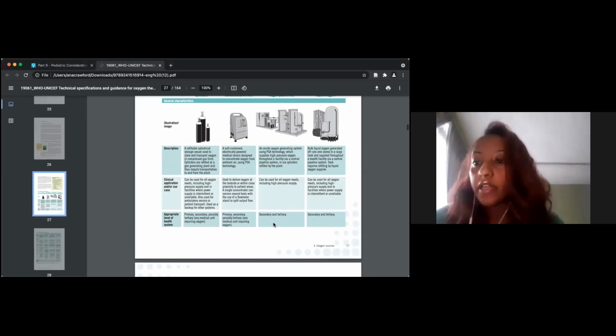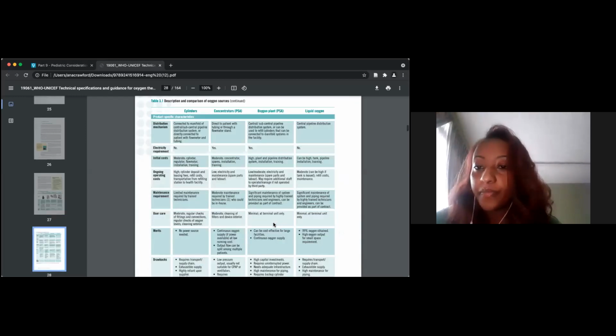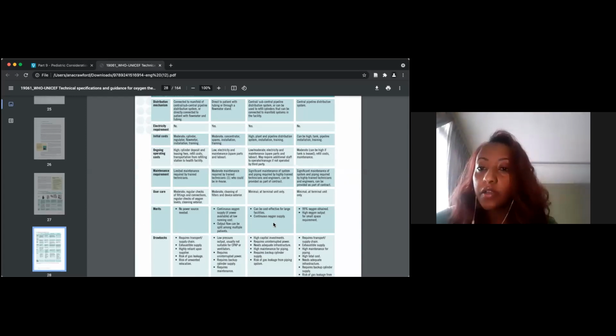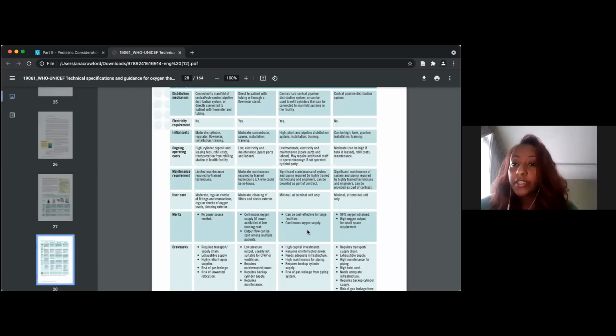And when it comes to distribution mechanism, cylinders are connected to a manifold of a centralized high pressure pipeline distribution system, or directly connected to a patient with flow meters and tubing. Concentrators are directed to patients with tubing through flow meters. These are some of the things that we know already, so I'm not going to go too much on it. But oxygen plants and liquid oxygen are central sources, usually subcentral, where you connect them to a bedside distributed system, or they can be used to refill cylinders that can be connected to a manifold system in the facility.